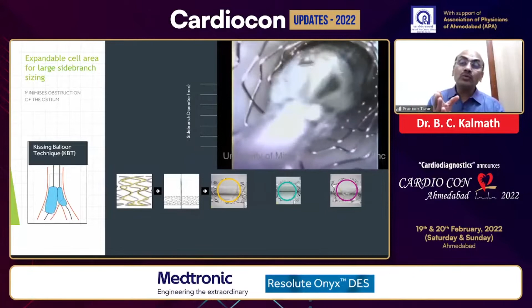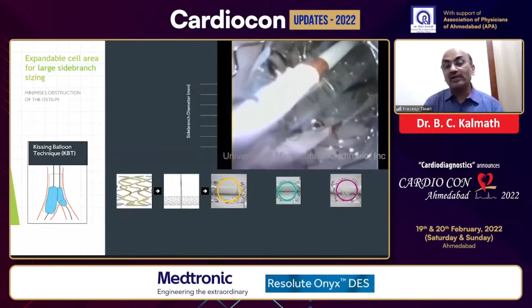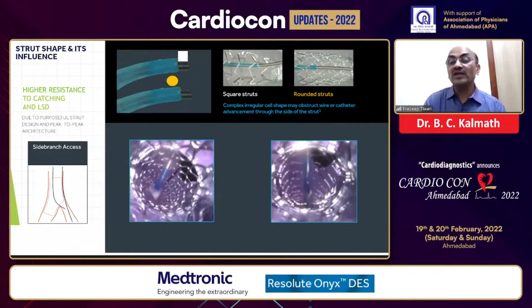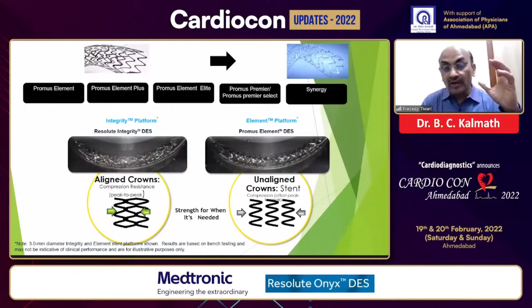And you could see how the stent conforms here, because of the single coil structure, which makes it beautifully adherent, and it also has great radial strength. Radial strength is comparable between them: 4.2 for the Synergy versus 4.1 for Onyx, so it also has good radial strength. And because the strut structure is peak to peak, there is less fracture, unlike the peak to valley of Synergy, which becomes a little hindrance here. So in this, the crowns are aligned peak to peak, which makes it more conformable, and the foreshortening also comes down.